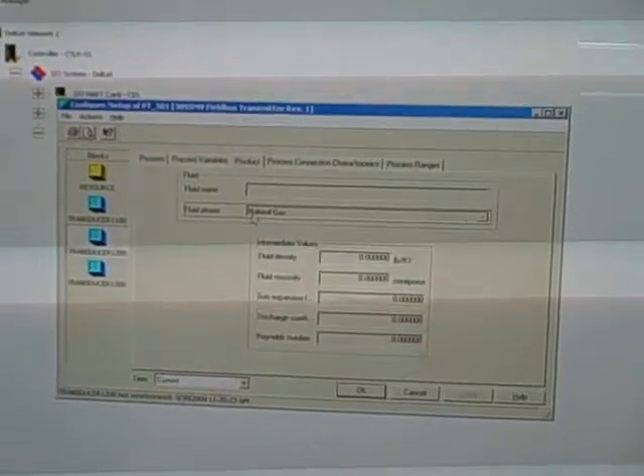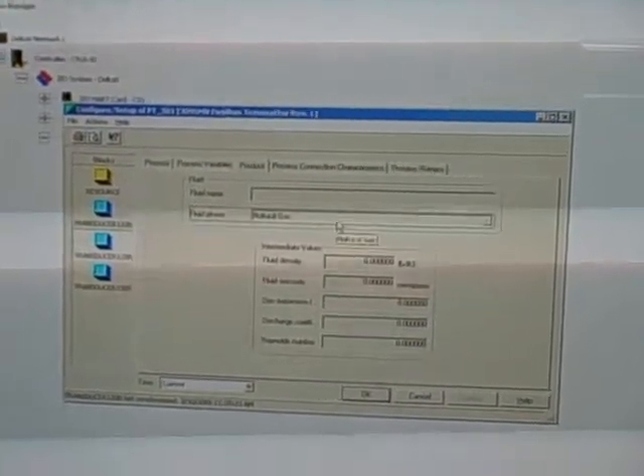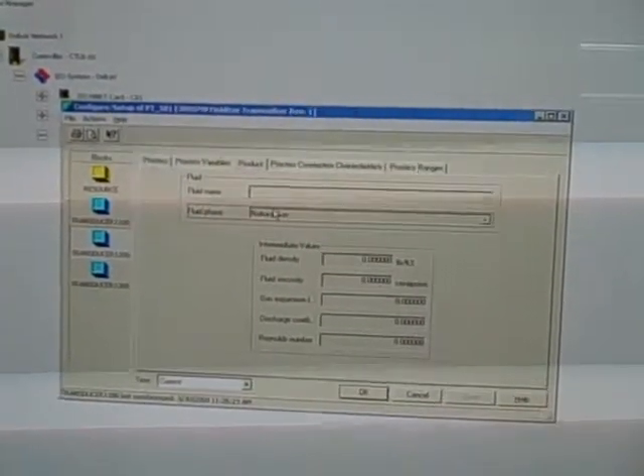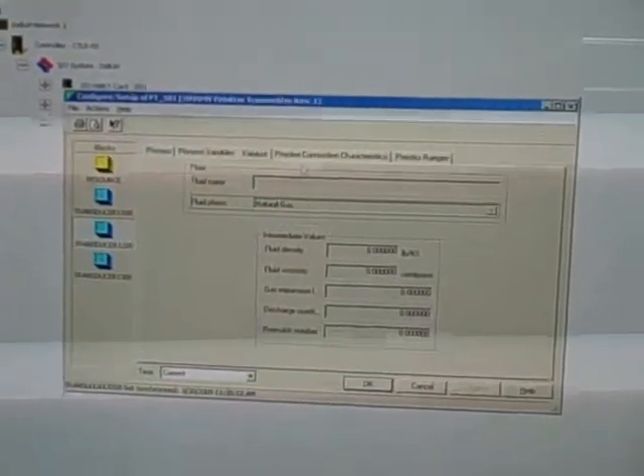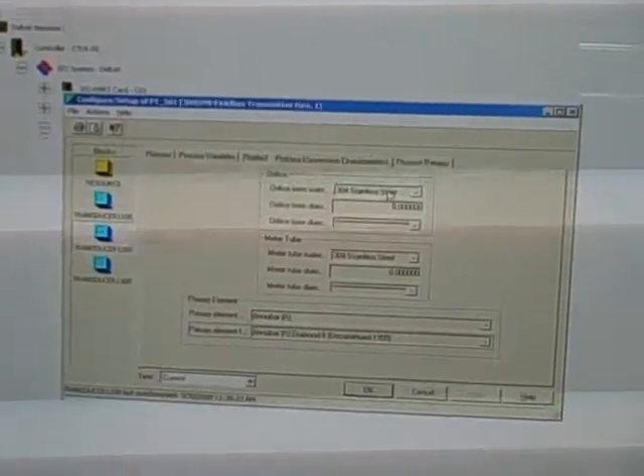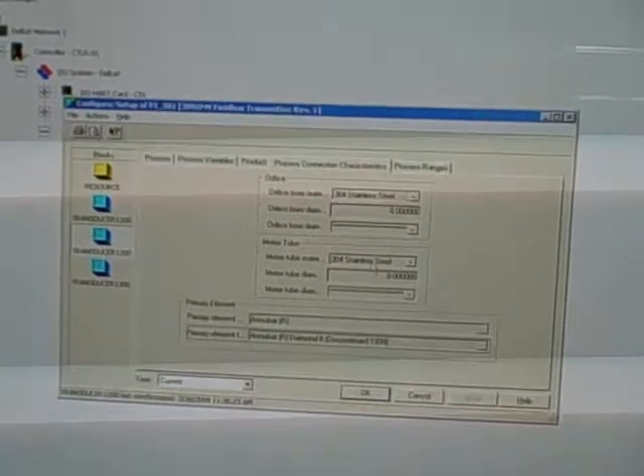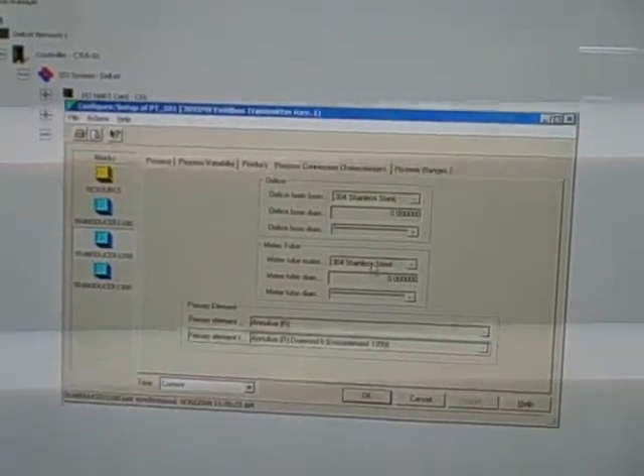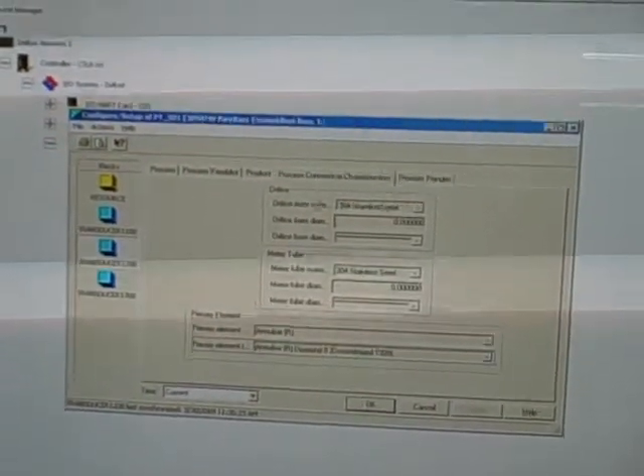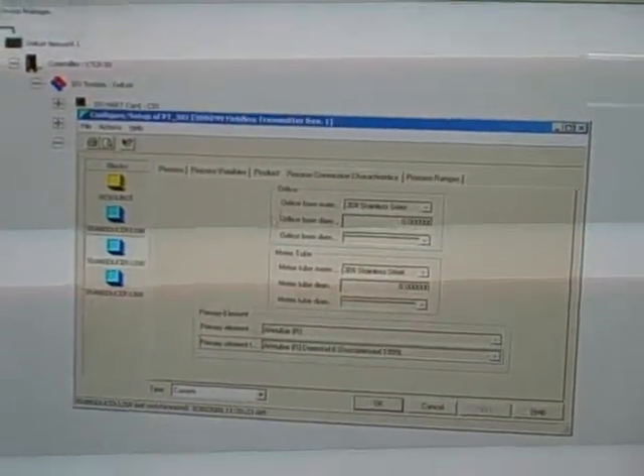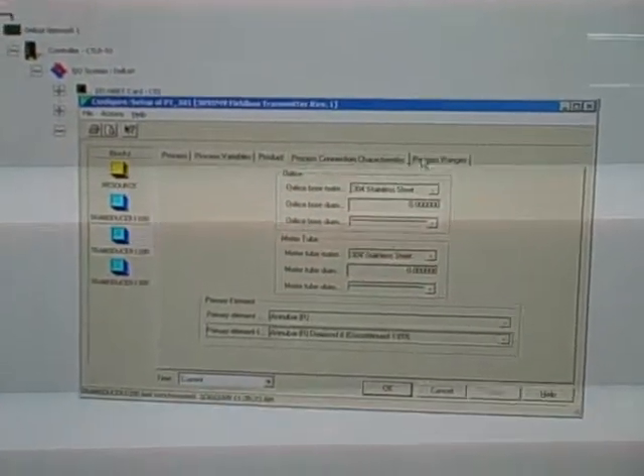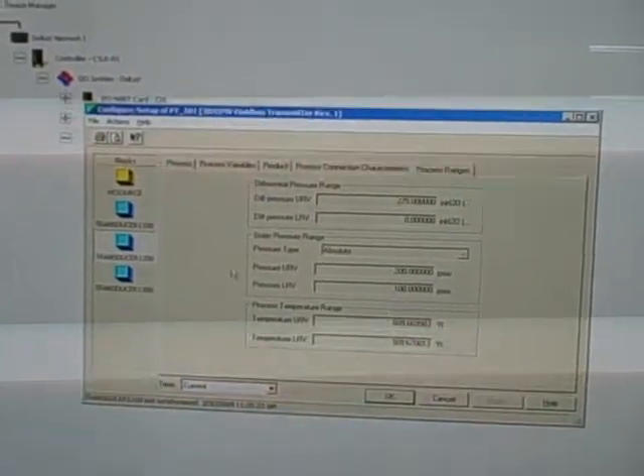We tell it what sort of fluid is going through it. In this case, natural gas is the default fluid. We give it some other information: the orifice plate bore diameter, the orifice plate material, the meter tube material, the meter tube diameter, and it will then go through the appropriate calculations to figure out mass flow rate. We also give it ranges here.